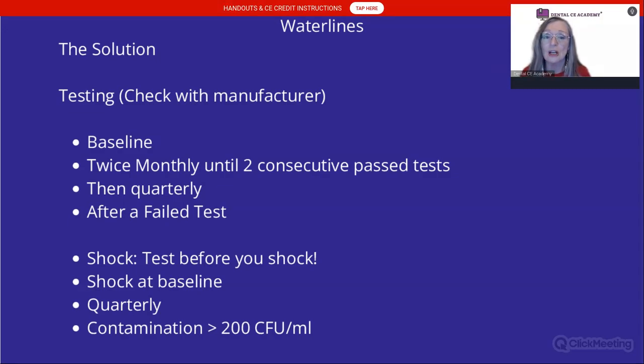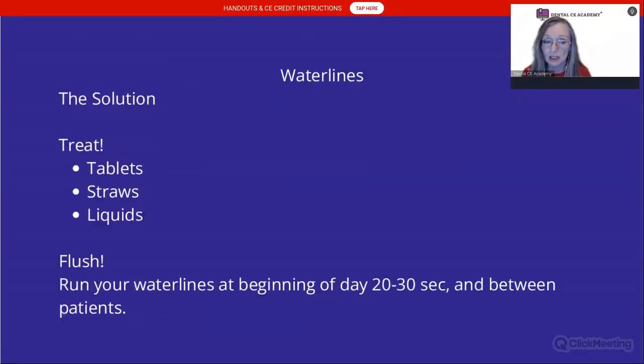So we have to test our water lines. Check with your manufacturer. Test at baseline. If you have not tested yet, start now. Then twice monthly until you have 2 consecutive pass tests. Then you'll test quarterly and always after a failed test. You always have to shock, but you should test your lines before you shock them at baseline, then quarterly. And if contamination occurs in your testing, over 200 CFUs per mL, you're going to need to shock. So you can still be treating your water lines and have a failed test. All right.